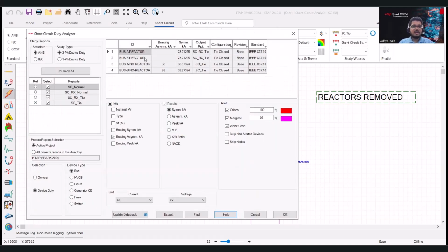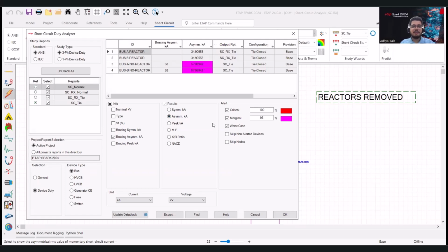Here we see the results for the substation model 1.0, model 2.0. We have the short circuit increasing significantly from 23,000 all the way to 38,000. But I still don't see any flags here. My system is still healthy. Everything looks fine. We can start the motor as well. So what's the issue? When I look at the asymmetrical fault current, this is where a flag pops up. We have the short circuit approaching marginal alert because my system is rated for a 58 kiloamp short circuit. The system fault current is about 57. This is too close to be comfortable and needs to be remediated.